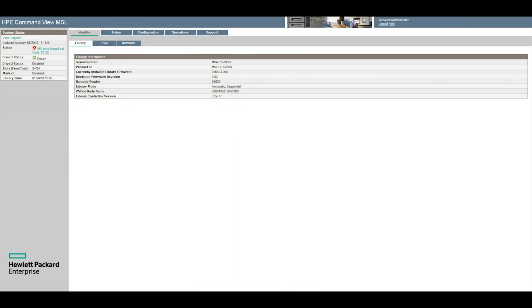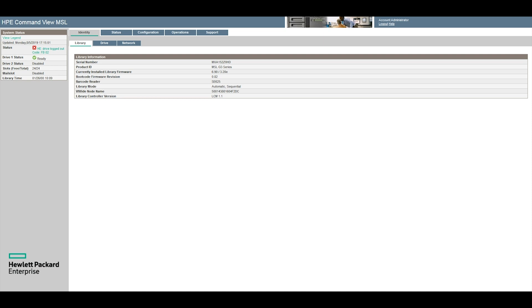The second way to identify a faulty drive is from the web GUI. After logging into the web GUI you will see the library and drive status window. This status window will list the current status of all drives in the library. These are in the same number order as they are listed on the front control panel of the library. If there is a fault on a drive it will be displayed here.